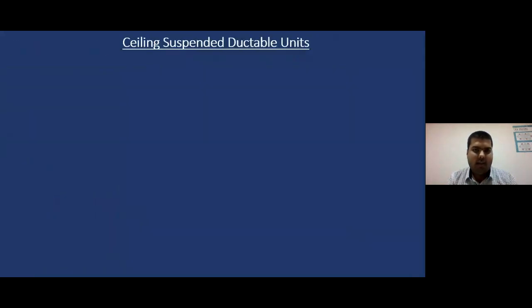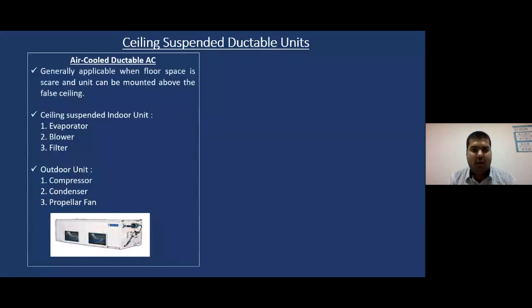Ductable units which are ceiling suspended. Basically in hotel applications where I don't have much floor space, which is again very costly, I can install a machine which can be accessed through the ceiling. The only thing I would require is a trap door for service point of view. My ductable machine's indoor unit would cater to the evaporator, blower and filter, and my outdoor unit would have the compressor, condenser and a propeller fan.